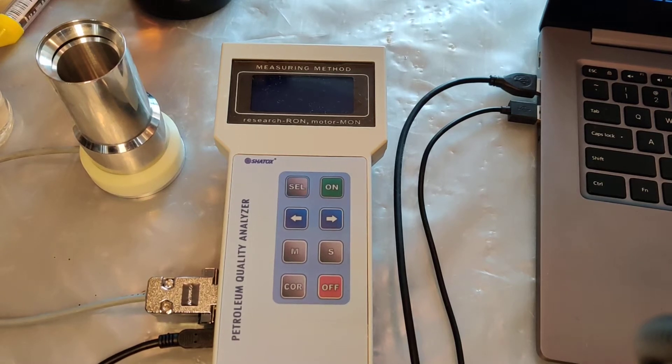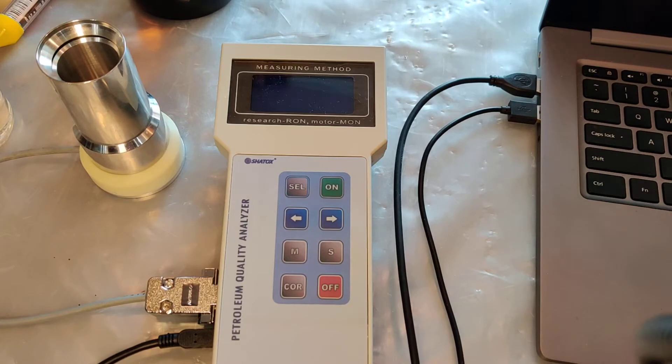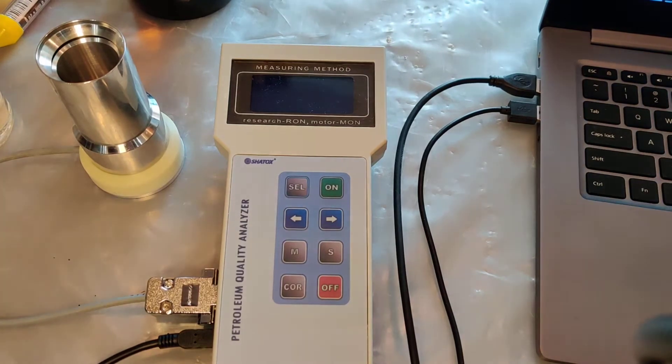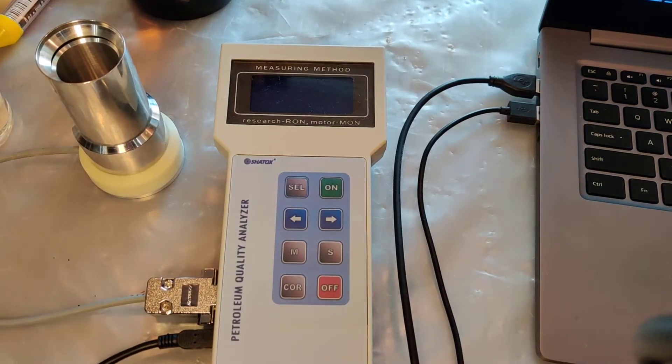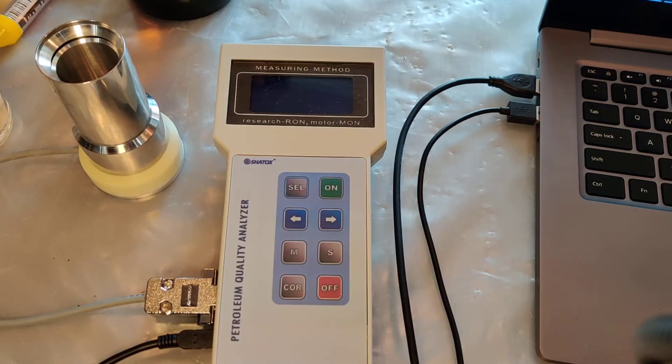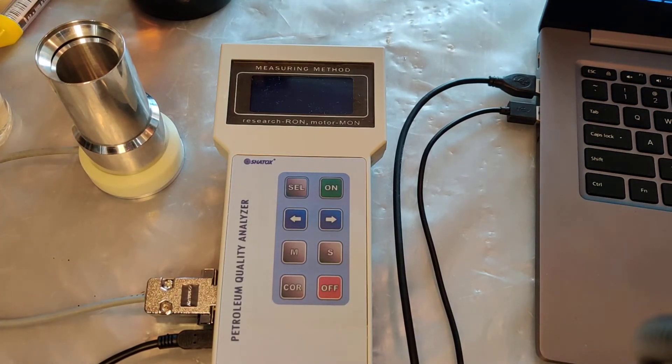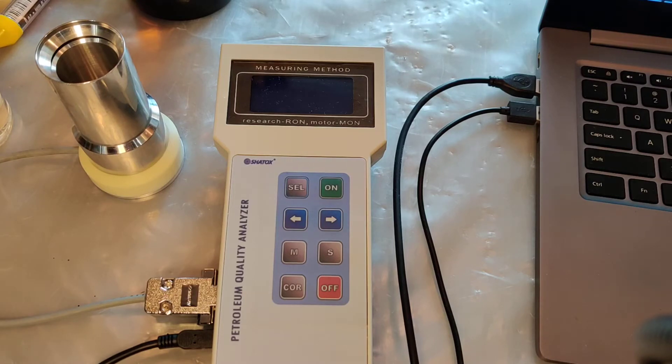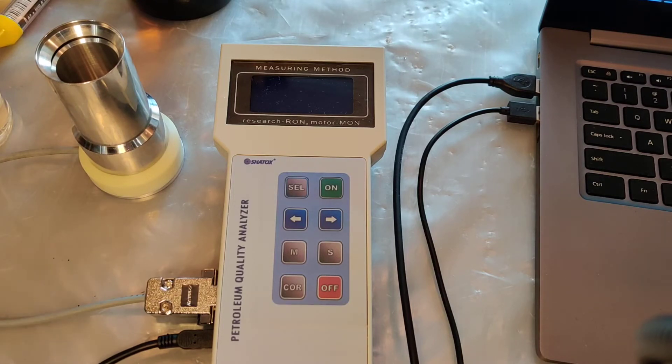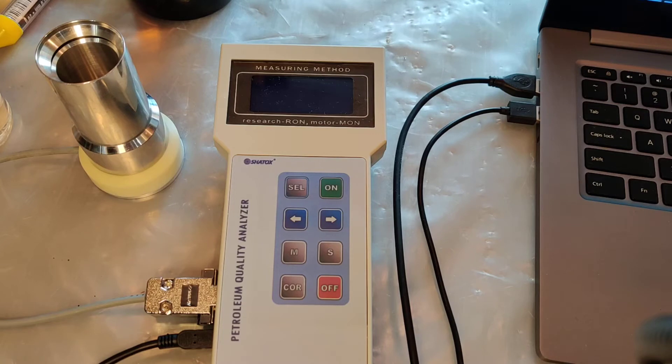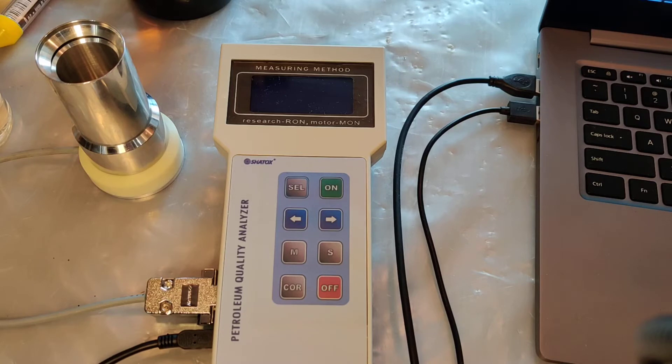Today I'm going to show you how you can easily calibrate the Octane Tester's sensor cup. There is a small hole in the bottom part of the sensor and by using a clock screwdriver you can rotate the screw inside the sensor and calibrate it.